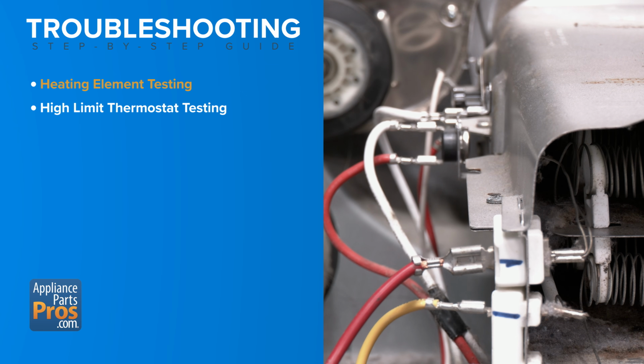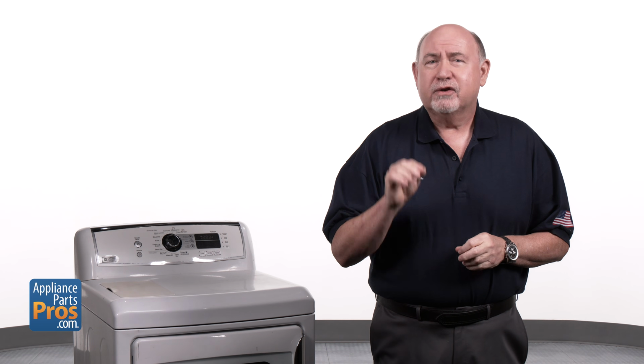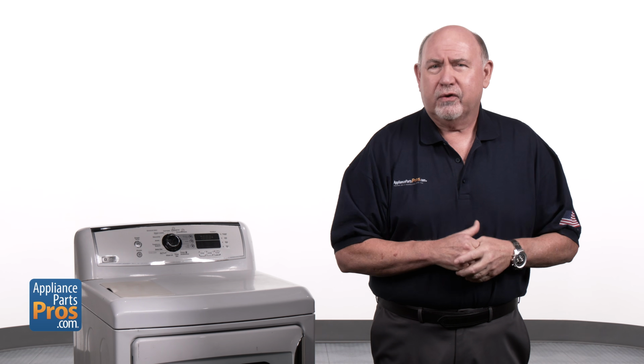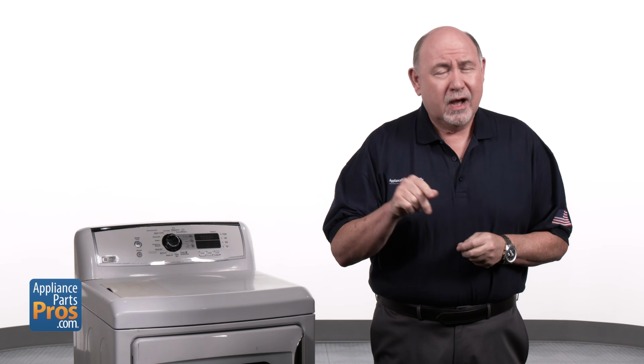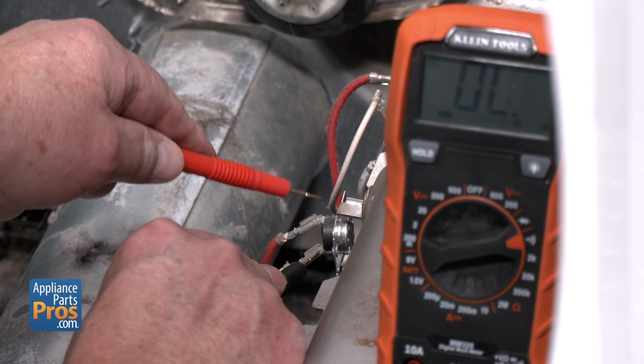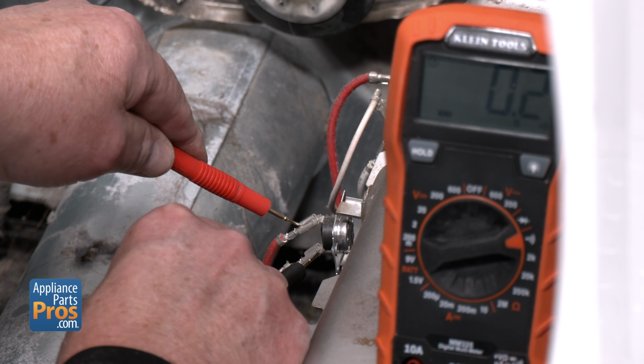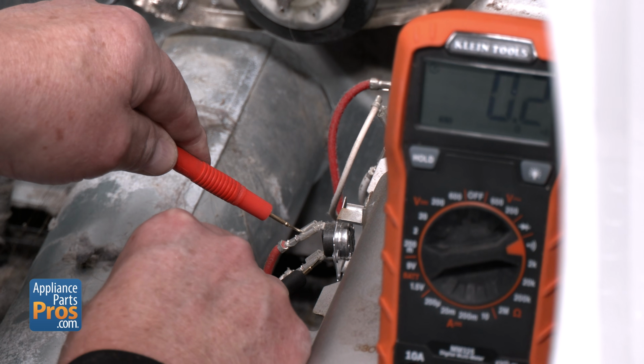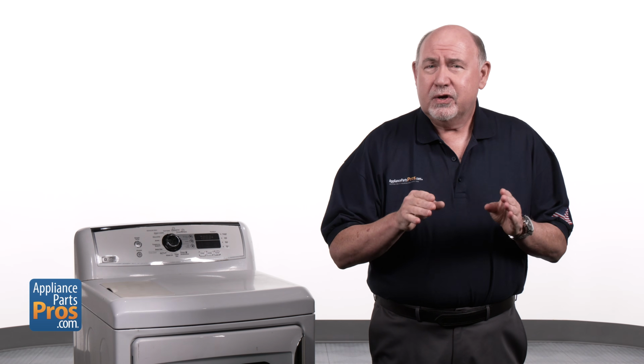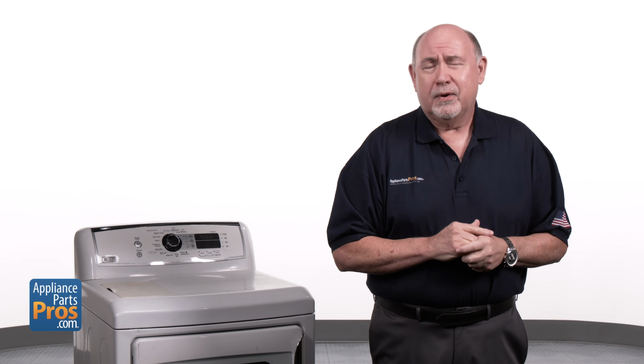The high-limit thermostat is located just behind the terminals for the heating element. On electric models, it trips at 284 degrees Fahrenheit and is not resettable. To check it, use your multimeter set for continuity. If it's open, it will need to be replaced. If it's good, we will need to move to another component.